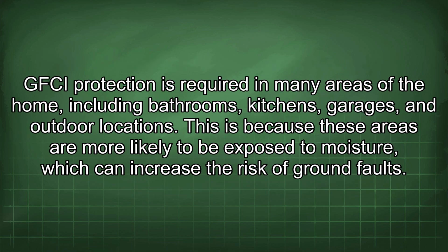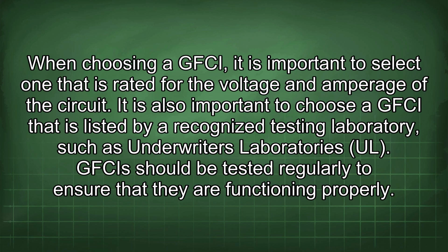GFCI protection is required in many areas of the home, including bathrooms, kitchens, garages, and outdoor locations. This is because these areas are more likely to be exposed to moisture, which can increase the risk of ground faults. When choosing a GFCI, it is important to select one that is rated for the voltage and amperage of the circuit. It is also important to choose a GFCI that is listed by a recognized testing laboratory, such as Underwriters Laboratories, UL. GFCIs should be tested regularly to ensure that they are functioning properly.